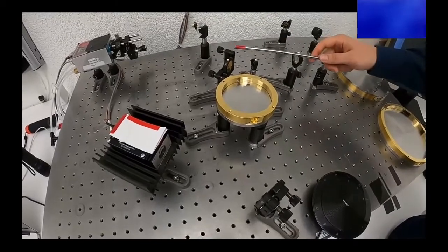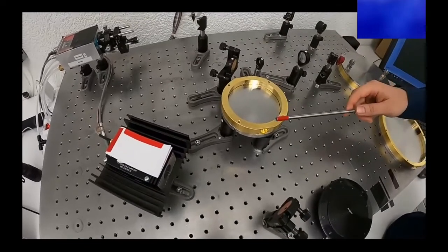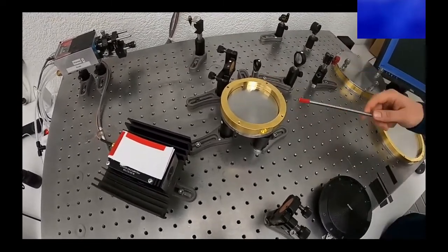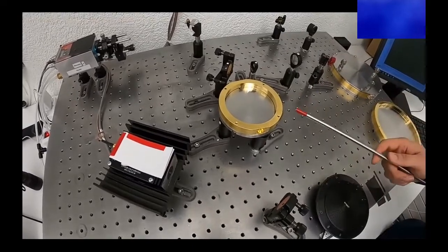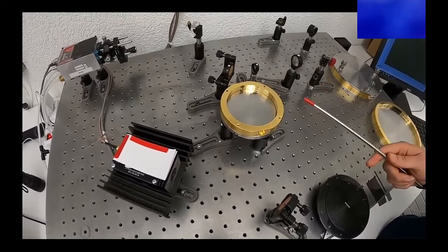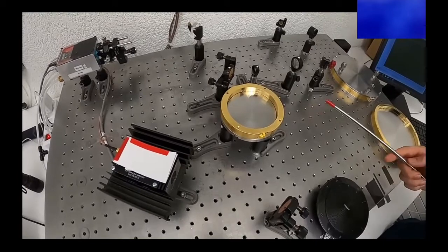Basically, when you do the alignment, the beam has to first hit a specific mirror, and after that it will bounce off each mirror exactly once. So in the case of the small cell, that will be the 4-meter version, that is 46 times, and in the case of the big cell, it's 86 times.